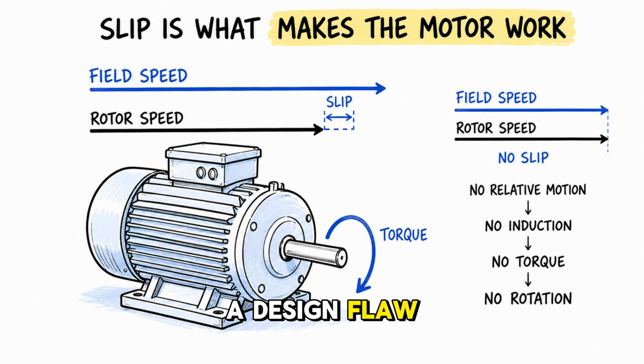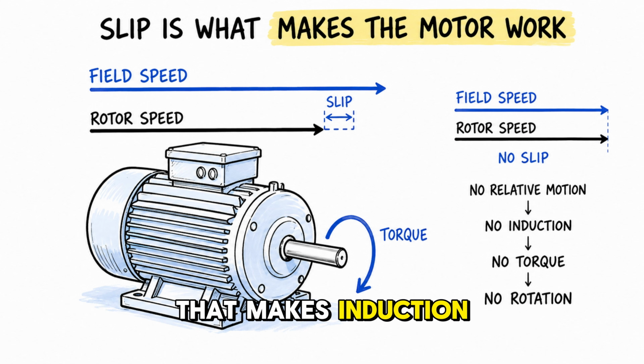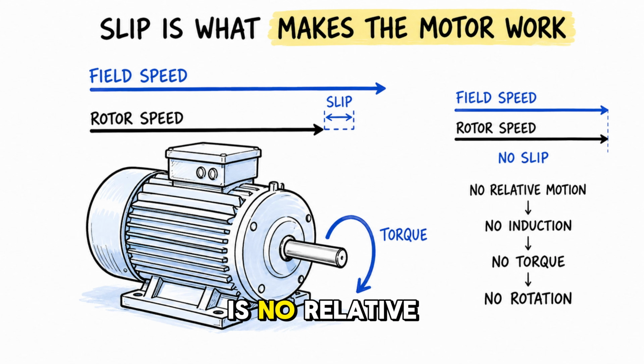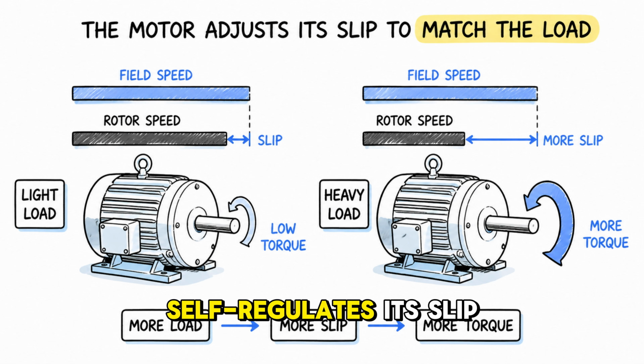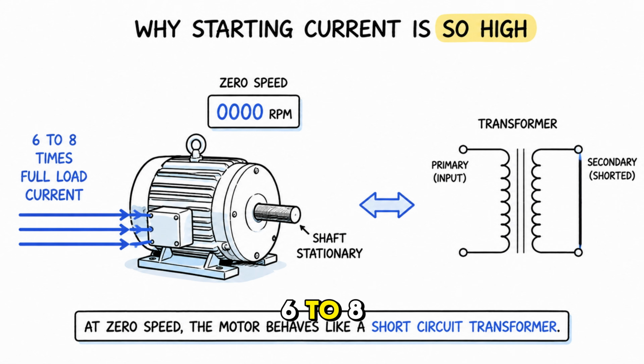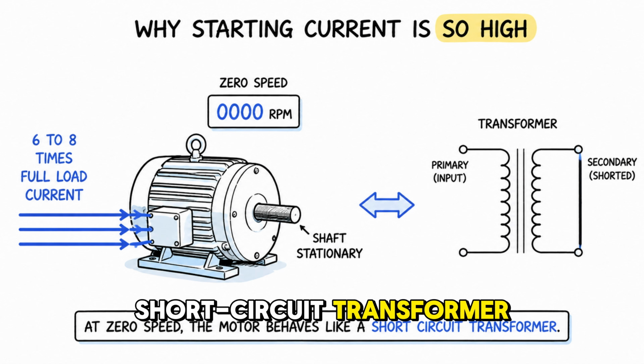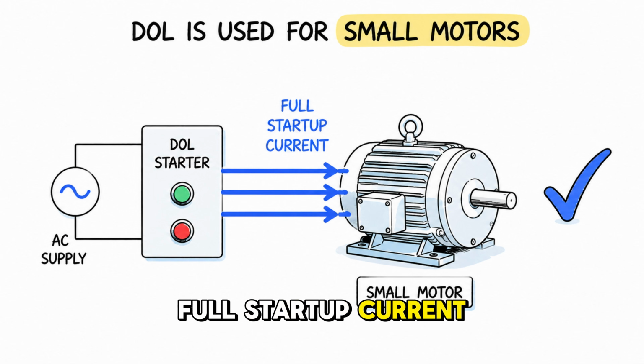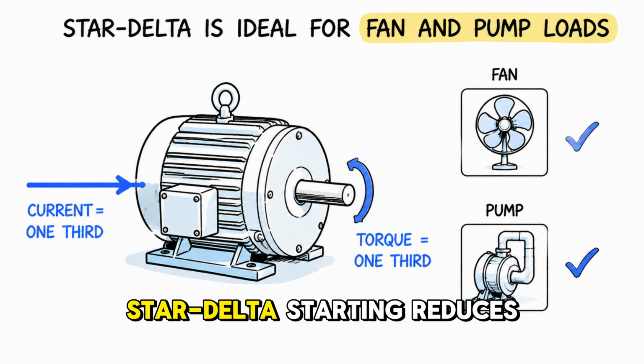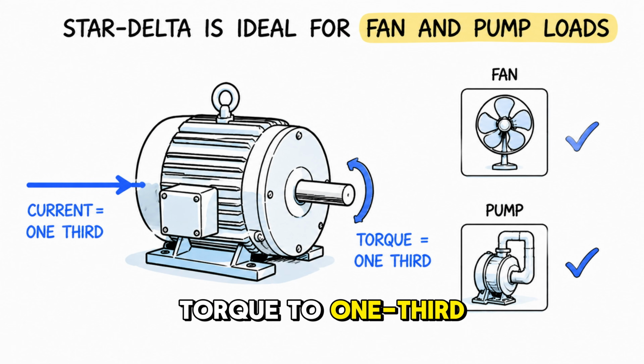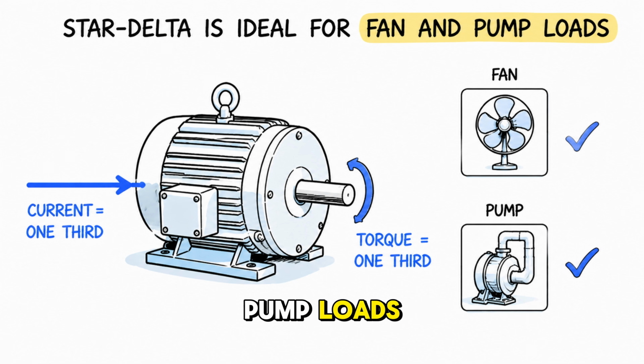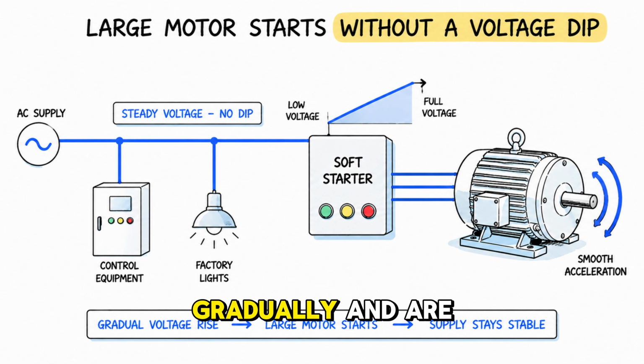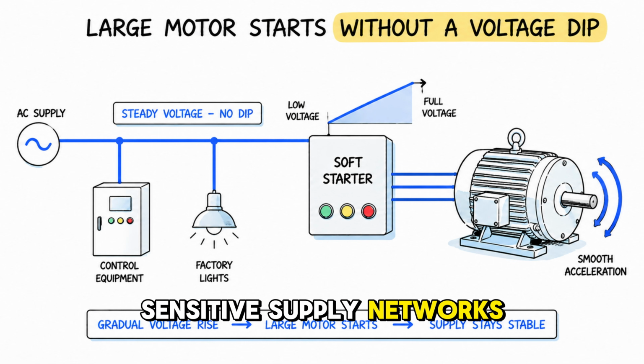Slip is not a design flaw. It is the fundamental operating condition that makes induction possible. Without slip, there is no relative motion, no induction, no torque, and no rotation. The motor beautifully self-regulates its slip to produce the exact torque the load demands. Startup current is 6 to 8 times the full load current because at 0 speed, the motor acts like a short-circuit transformer. DOL starting allows full startup current and is only used for small motors. Star delta starting reduces both current and torque to 1/3, making it perfect for fan and pump loads. Soft starters ramp the voltage up gradually and are used for large motors on sensitive supply networks.